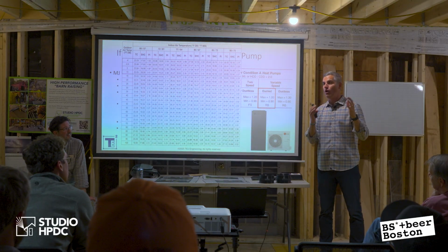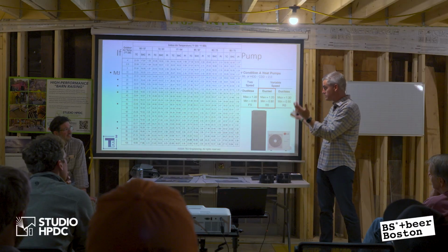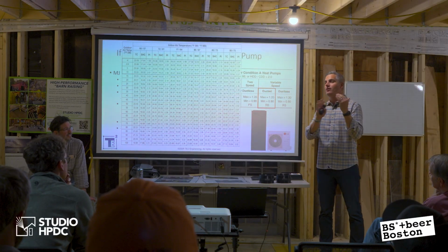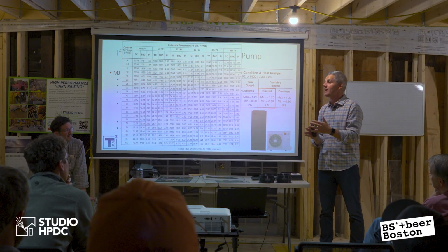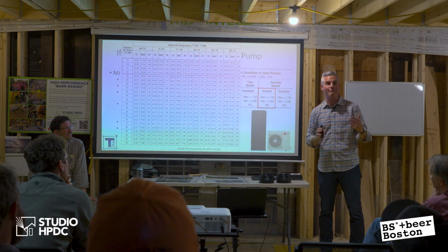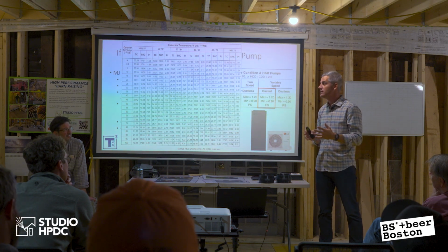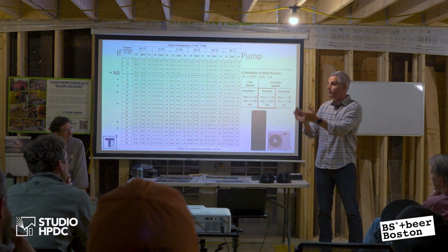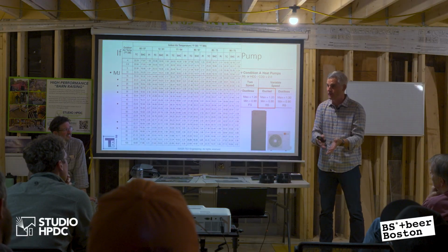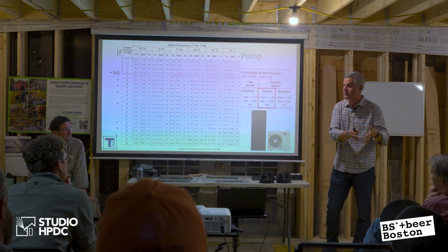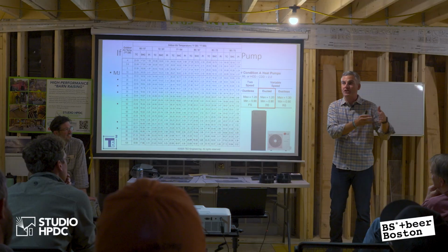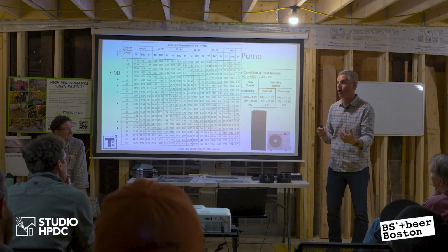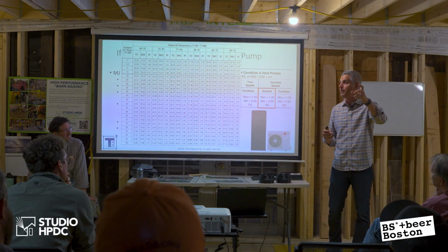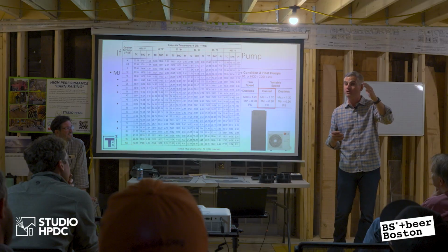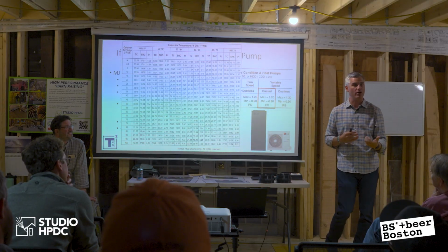And the trend is that all these manufacturers of mini splits, ducted splits, they're going to higher and higher sensible heat ratios. And the reason they're doing that is because they get better brownie points. They get better SEERs and EERs. Right. So the rebates offered by the utility companies incentivize manufacturers to go to higher and higher SEERs and higher EERs. So what they do is they say, hey, I'm not going to run the compressor as hard, and I'm going to warm that coil up, and therefore if the coil is not as cold, it's not going to wring out as much moisture when it runs.